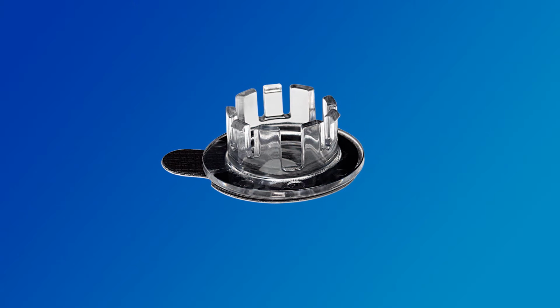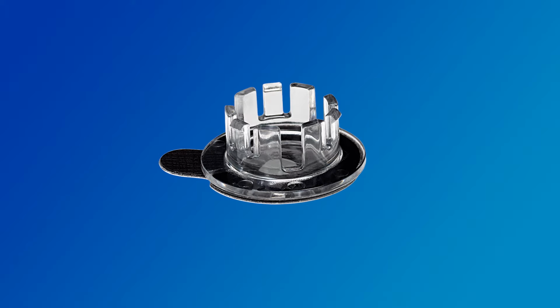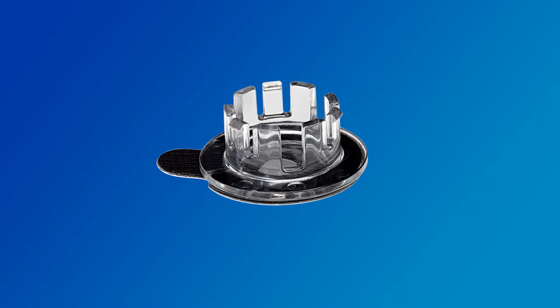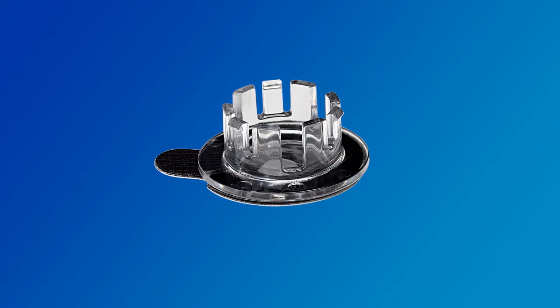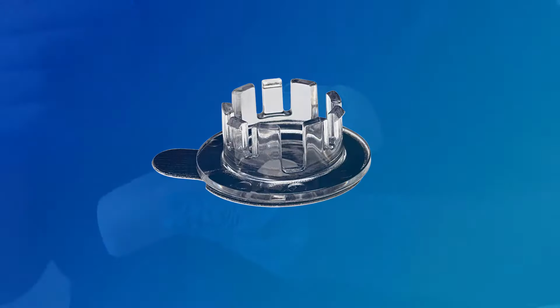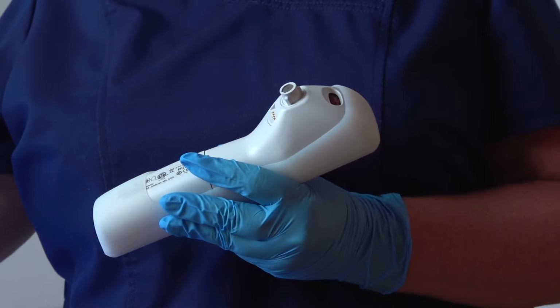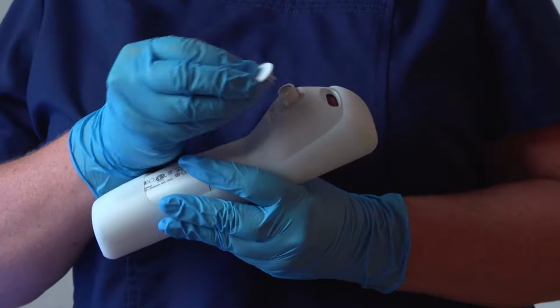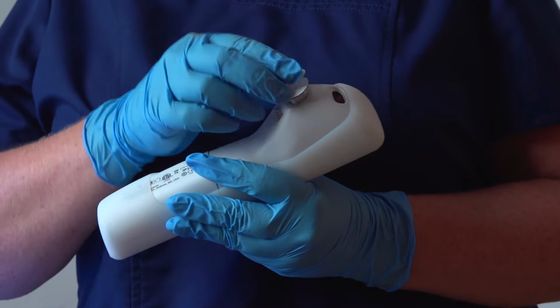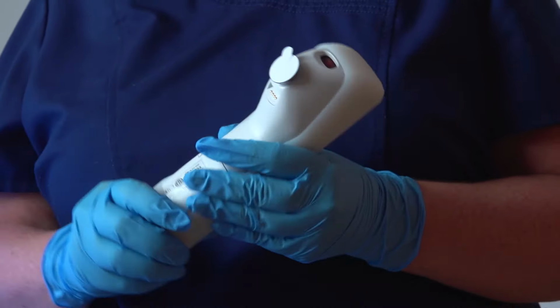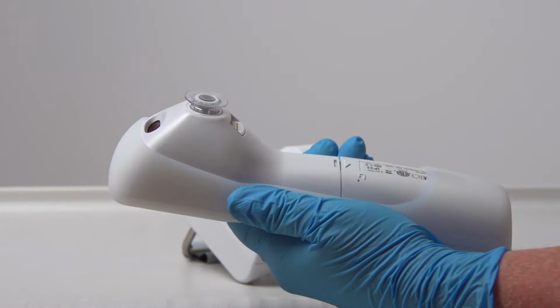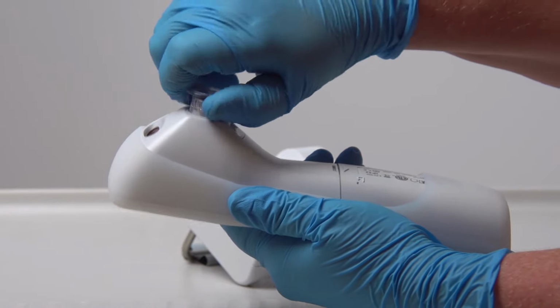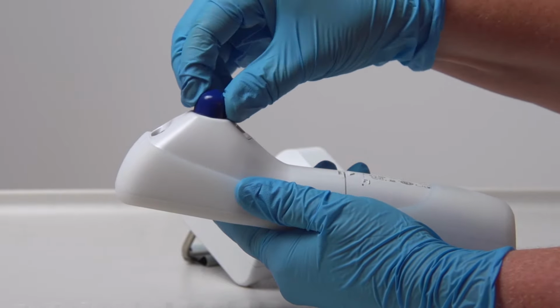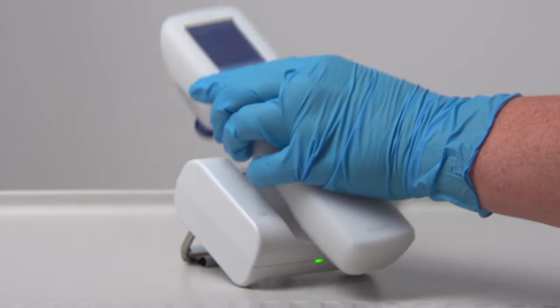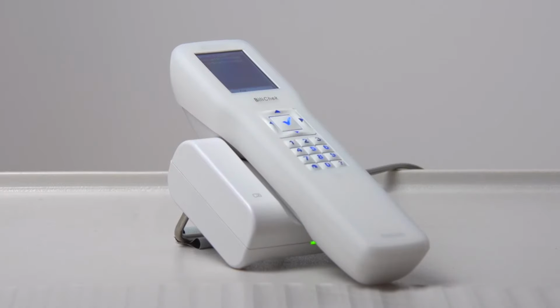The Bilichek uses a reference standard, the BiliCal, during each clinical measurement, reducing device performance variations over time. A calibration measurement using a new BiliCal calibration tip is required before each patient measurement to facilitate the Bilichek's accuracy. Using disposable tips decreases the risk of infection from cross-contamination associated with multiple patient devices and supports your facility's hospital-acquired infection initiatives.